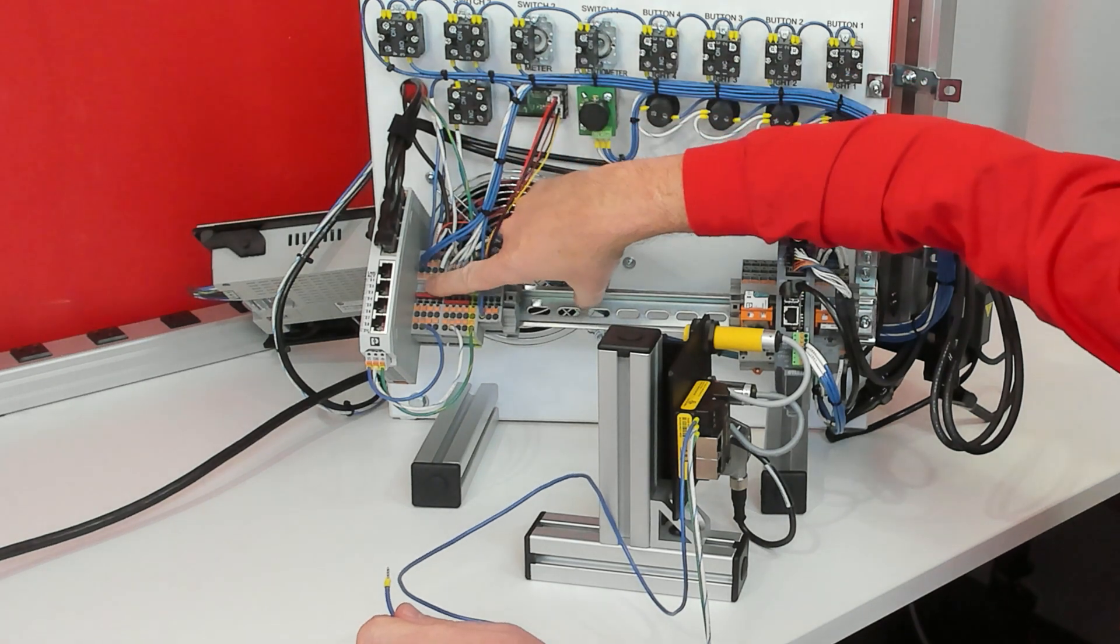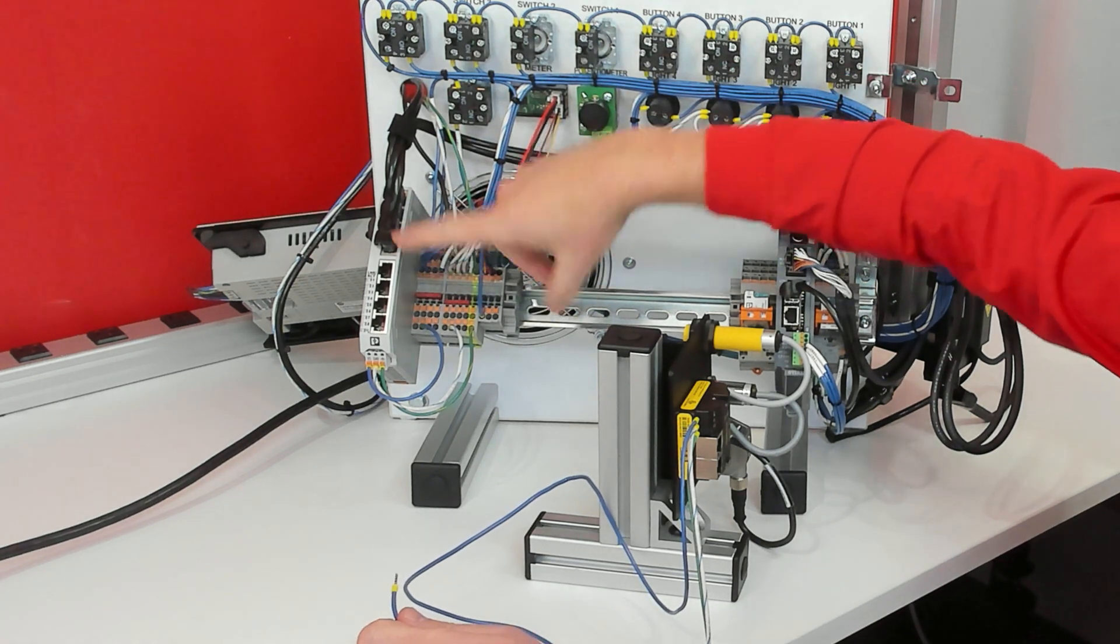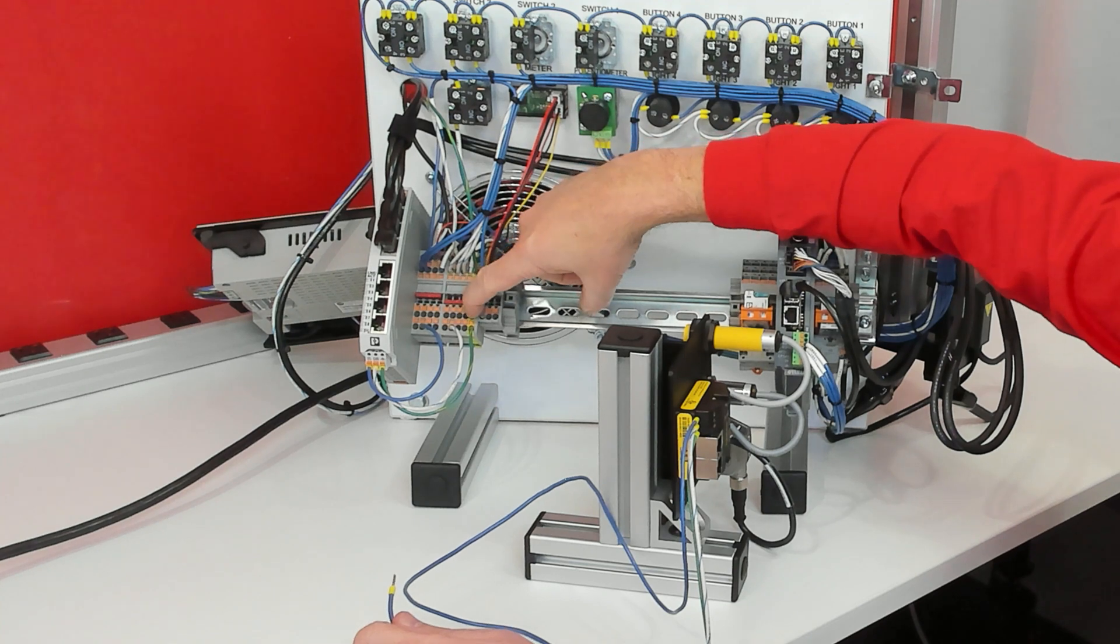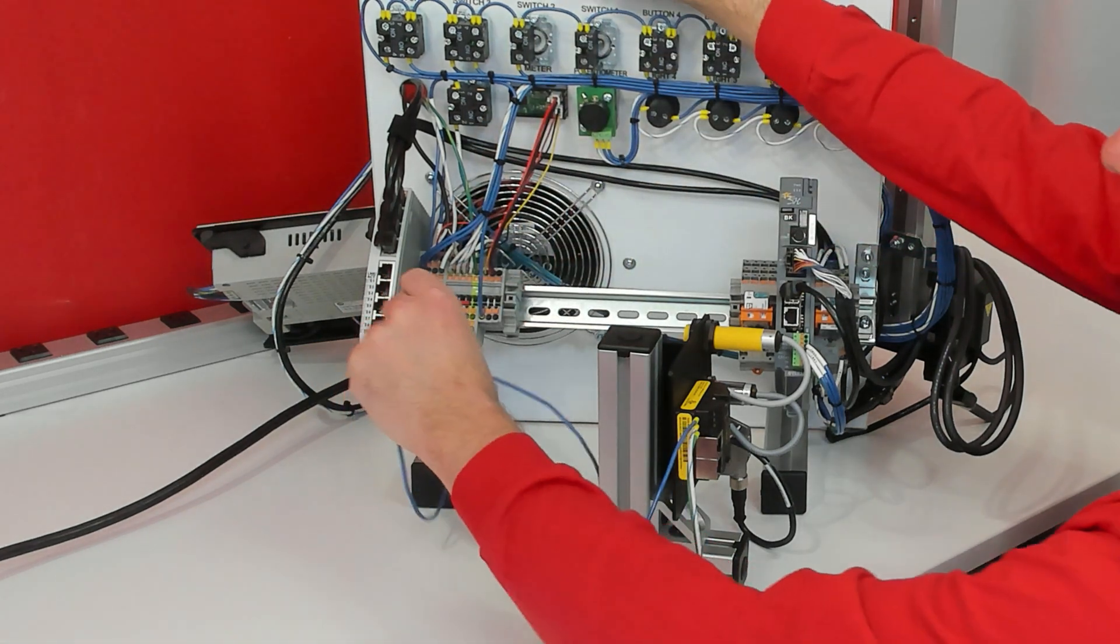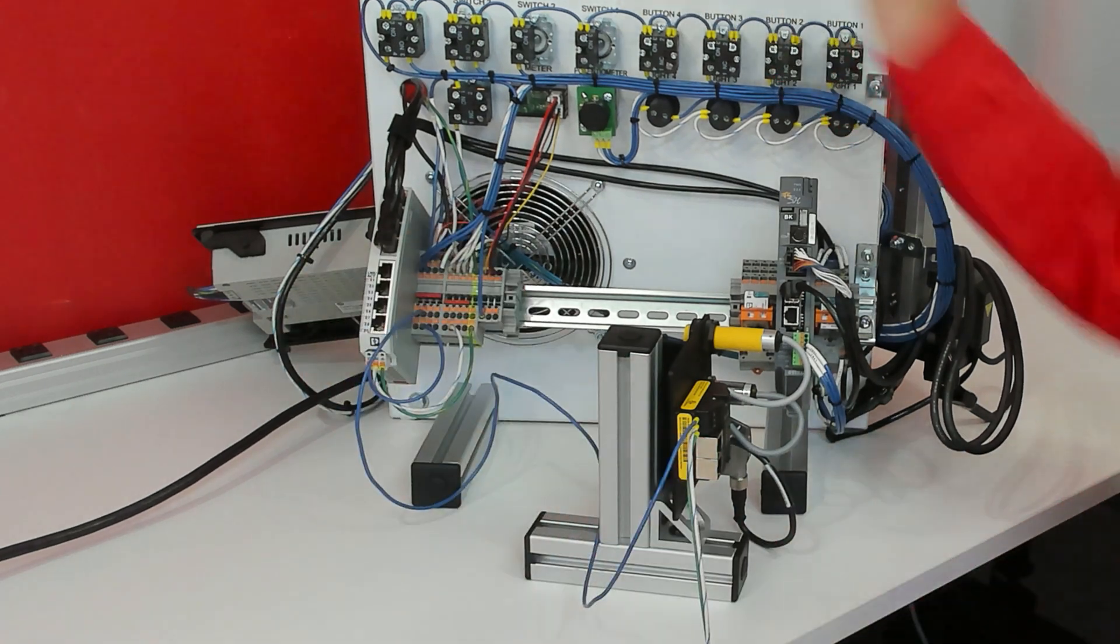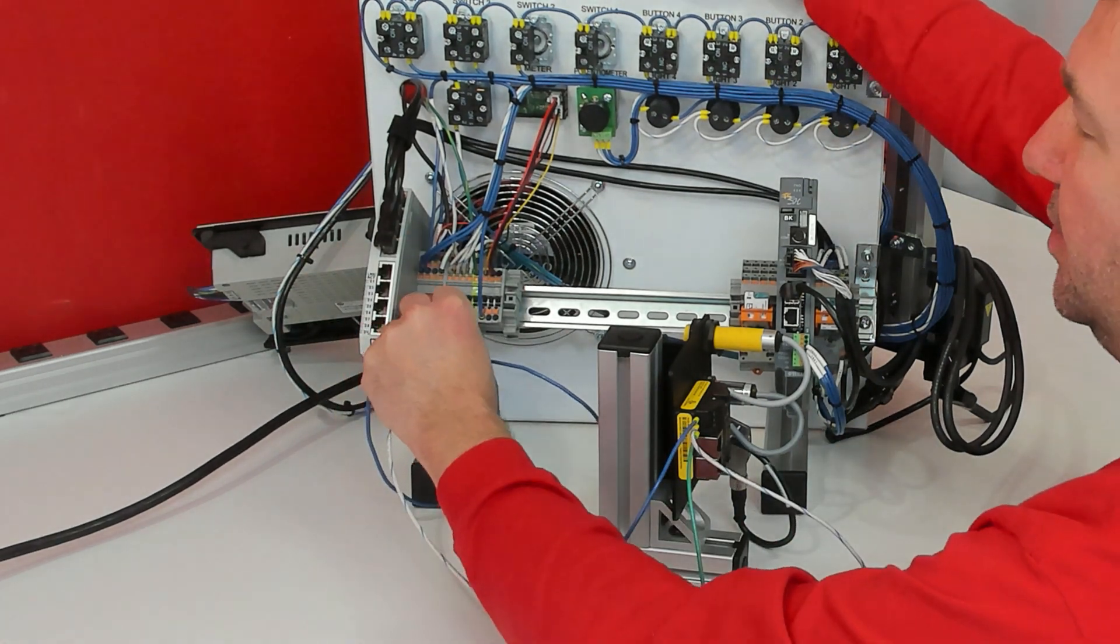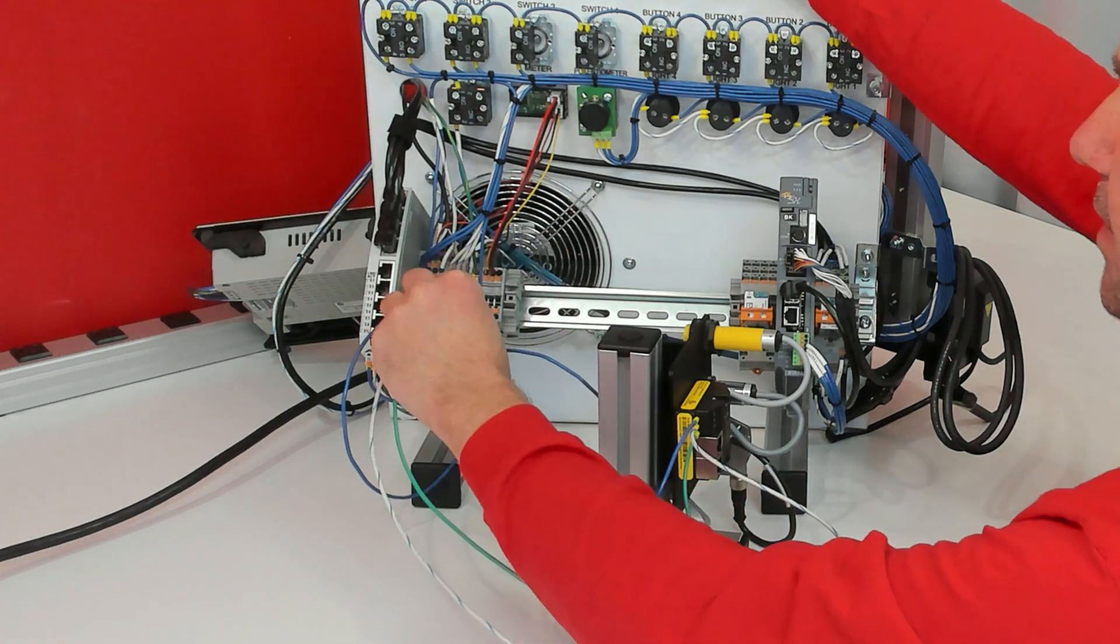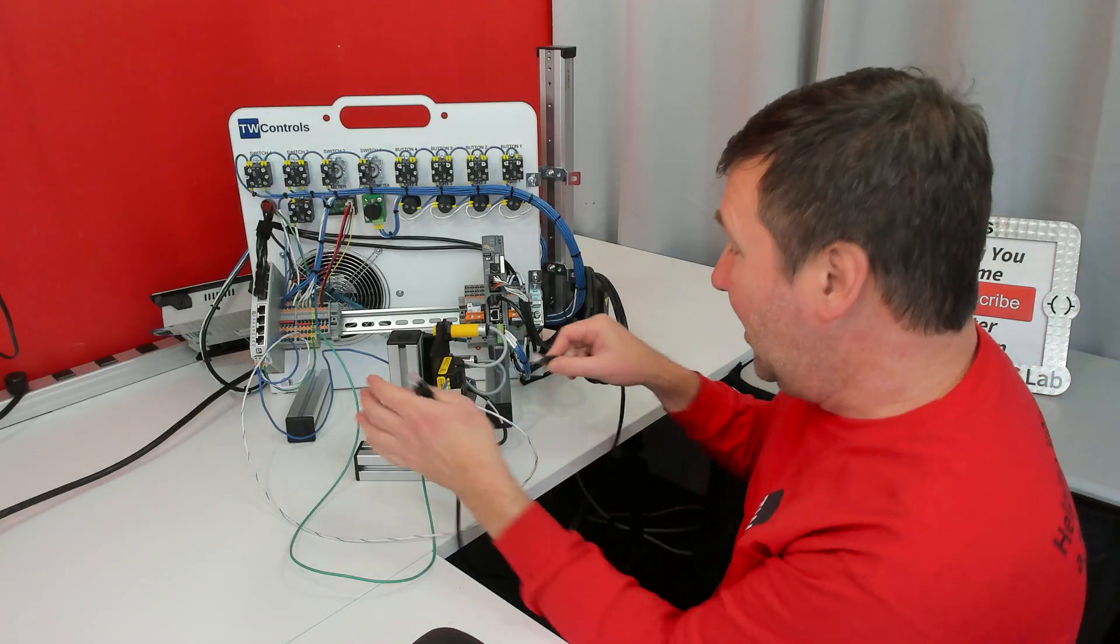Then on your PLC trainer, the left set of terminal blocks is your plus 24, the right set is your minus, and the green is your ground. So plug the blue wire into the left side of terminal blocks, the white wire into the right side of terminal blocks, and the green wire to the ground.